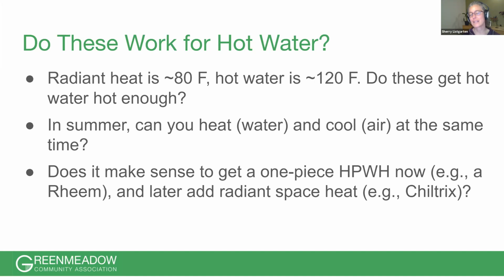I think it's right, and it is important to size your heat pump water heater properly, and maybe get the mixing valve so that you can heat it even higher so you don't run out. Because if you run out of quote gas in an EV, you're in a worse situation than if you ran out of gas in a car. So if you are moving it all the way to 140 degrees, that is the element - our little heat pump part is not getting it to that temperature. We're using the element to push it to that temperature; we can't do it with the heat pump, and then it's less efficient. The COP is getting kind of close to the element even with a heat pump, less than 2.